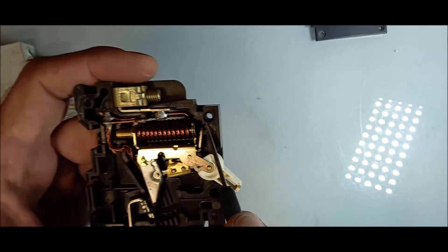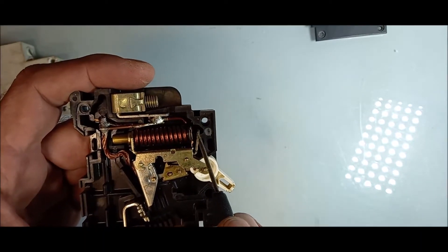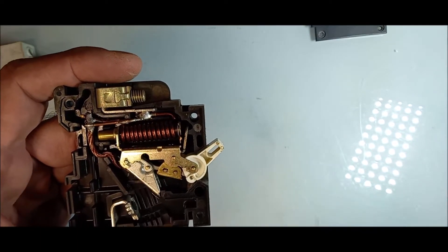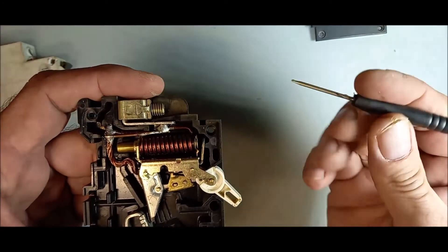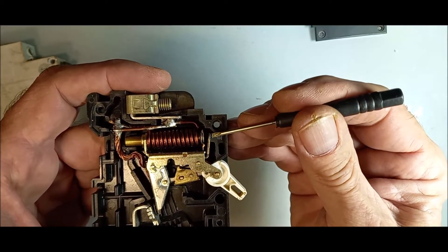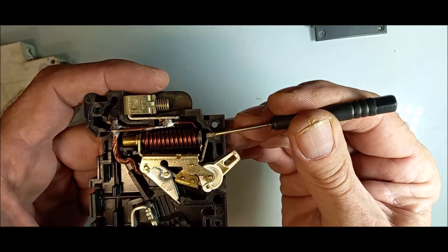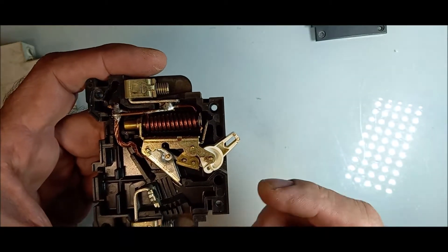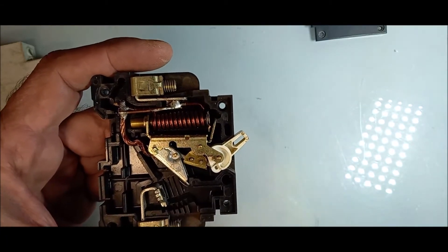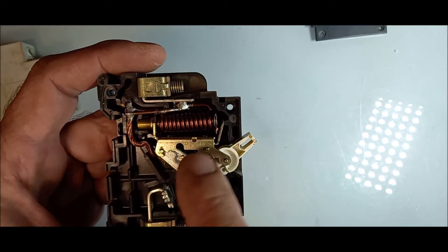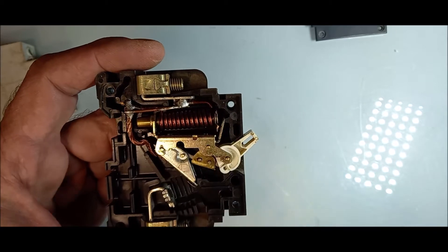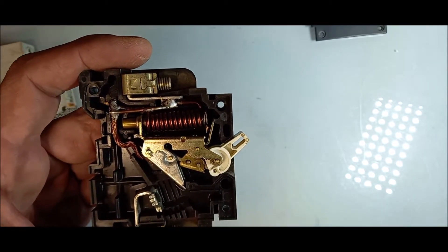And when I press that button, look what's going to happen. And then it goes back. You arm it. There's a maximum current through it. It pulls in, and then it releases and it opens here. This is how this device, the first of this two devices inside this trip switch working.